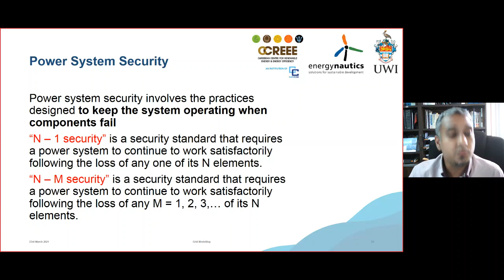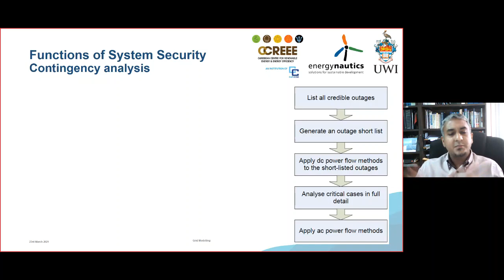We talk about contingency analysis. Now I have a diagram, a flow here, for contingency analysis. The most important thing to identify is that contingency analysis is a series of simulations you're going to perform based on a listing of credible outages. These disturbances are likely to happen, and you want to evaluate the performance of your network before they arise, so you have a better appreciation of how the system will respond. So we collectively refer to this as a defensive approach to power system operation.